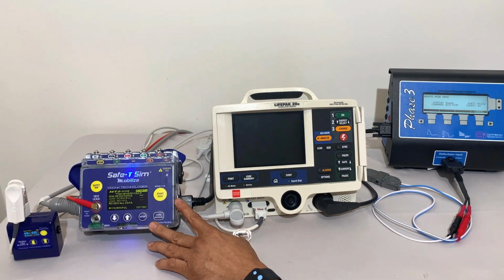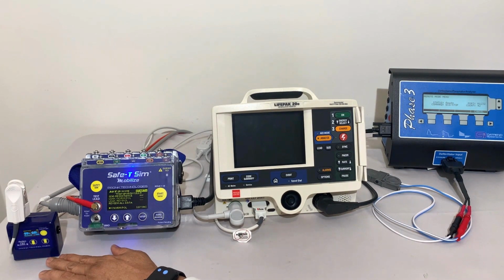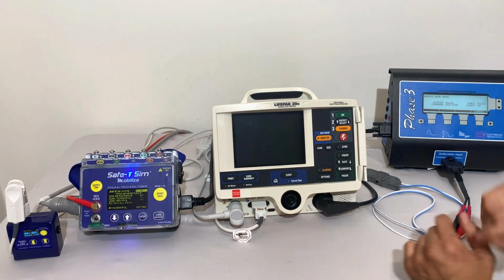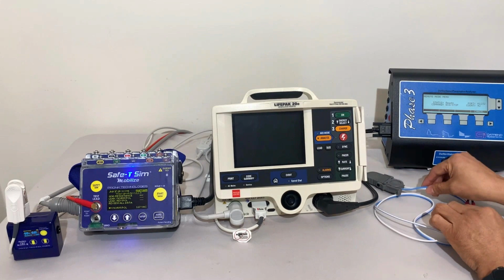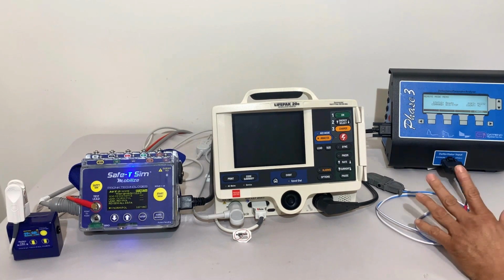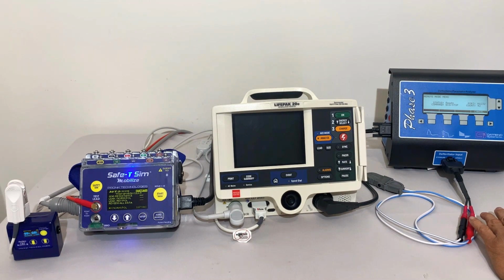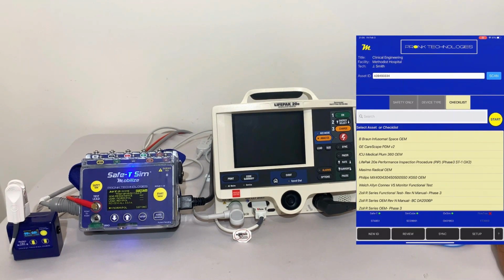It's ready to go. We've also connected the SpO2 parameter, which this defibrillator has, to our SpO2 simulator here on the left. And we've also connected the quick combo cable up to our defib analyzer here, so we can do the important discharge shock test and the pacer test, as well as the ECG gain test on the device itself. We're also going to be utilizing our Mobilize app here, which will allow us to have a lot of confidence in how we're going to perform this test, because we're going to be able to actually see and run and execute the actual manufacturer's procedure step by step, including what are the pass-fail parameters, to give us confidence that we've done all of the testing and that it meets the manufacturer's requirements.